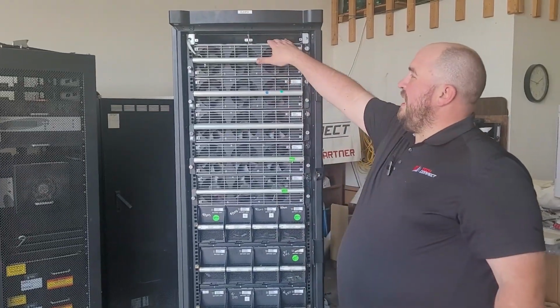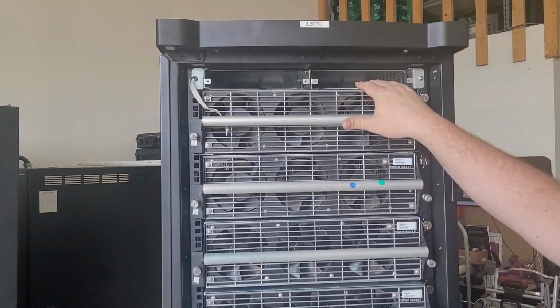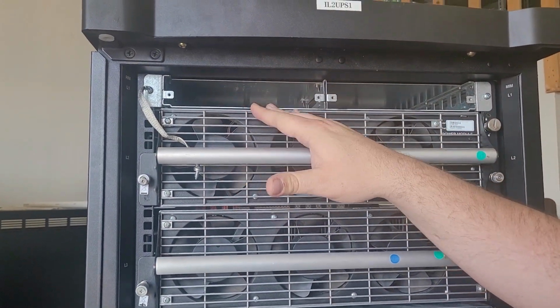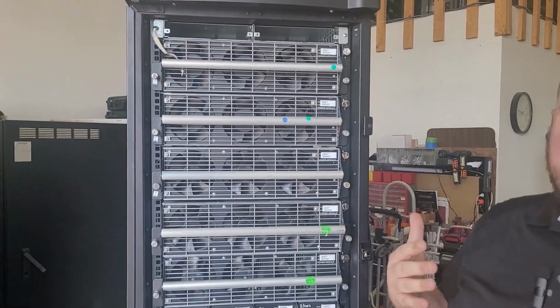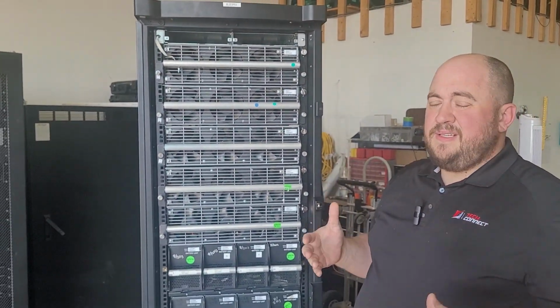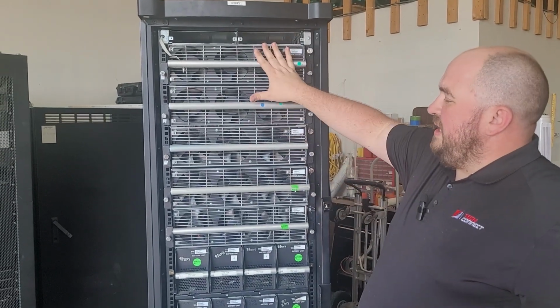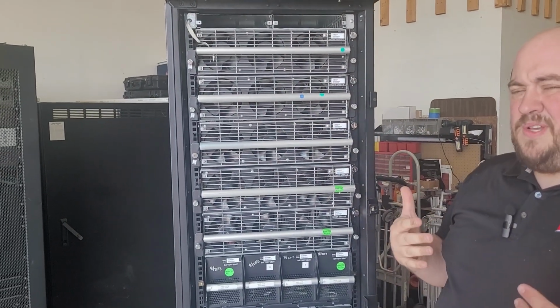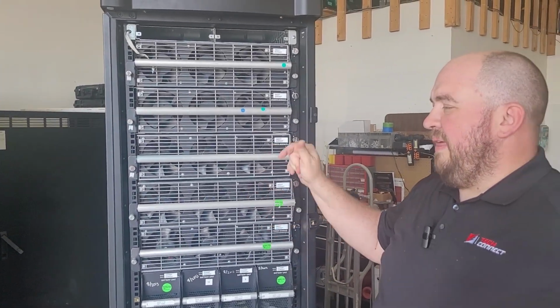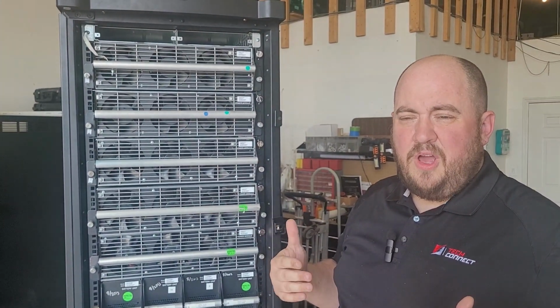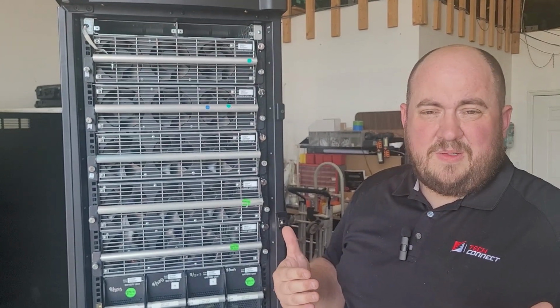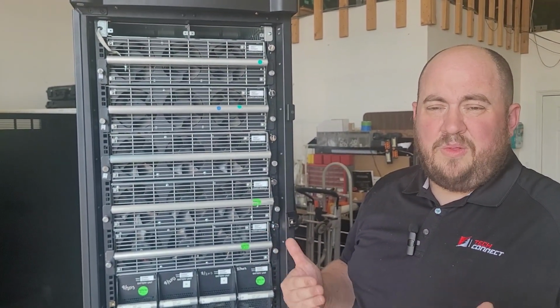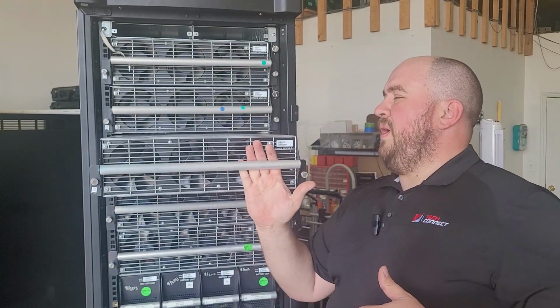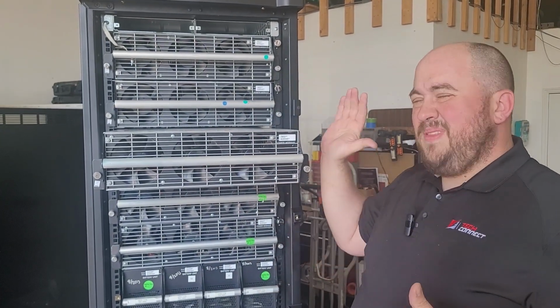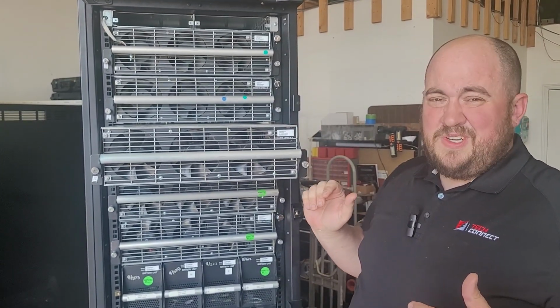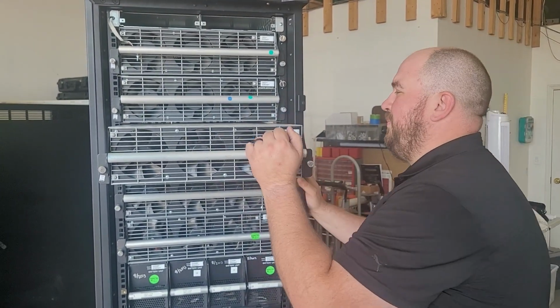So with these units up on top and these empty bays, we usually have intelligence modules. We have a main intelligence module and a redundant intelligence module. Those are the controls. Those are the brains for the system that tell it to operate, that monitor, that do all the heavy lifting. Underneath here, these power modules, I mentioned that we had N+1 redundancy. That means that these can fail and the other ones will seamlessly pick up the load, turn on, take over, and without you having to change anything out, without it going down or without a problem. It's just as simple as pulling one out, putting the other one in. I say that, but these modules are about 50 pounds or so, you probably need a couple of guys. They're pretty big and awkward.